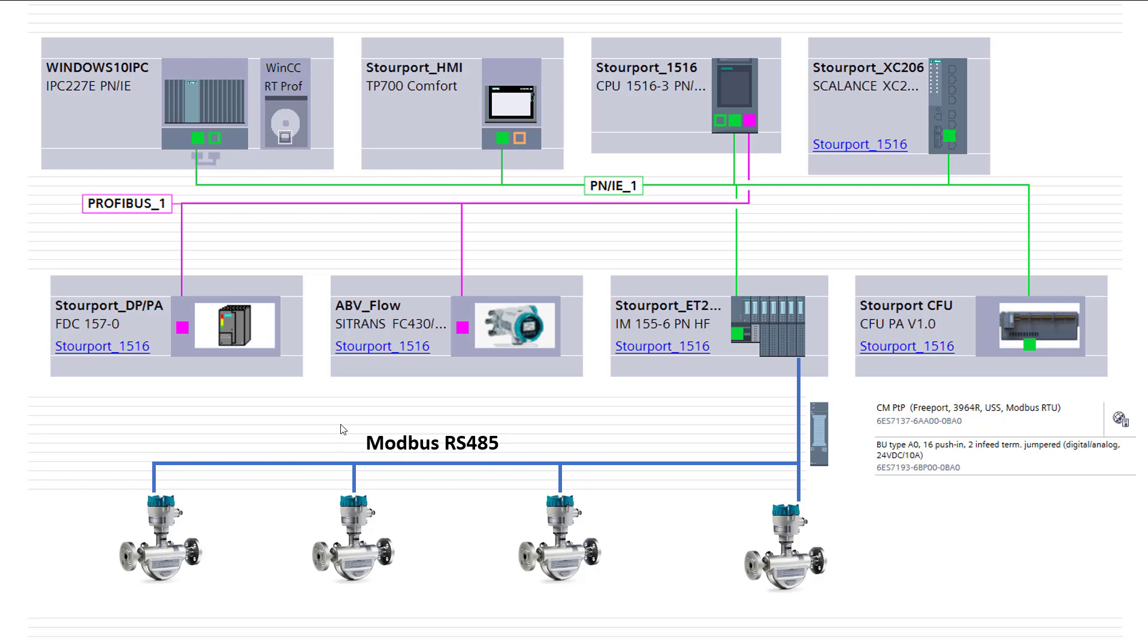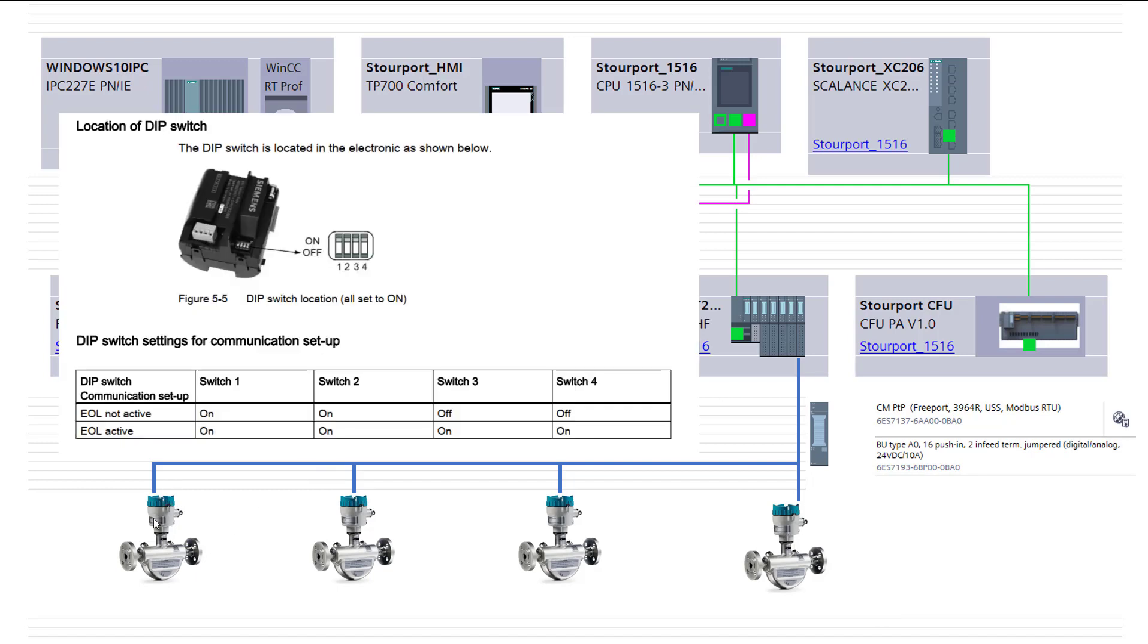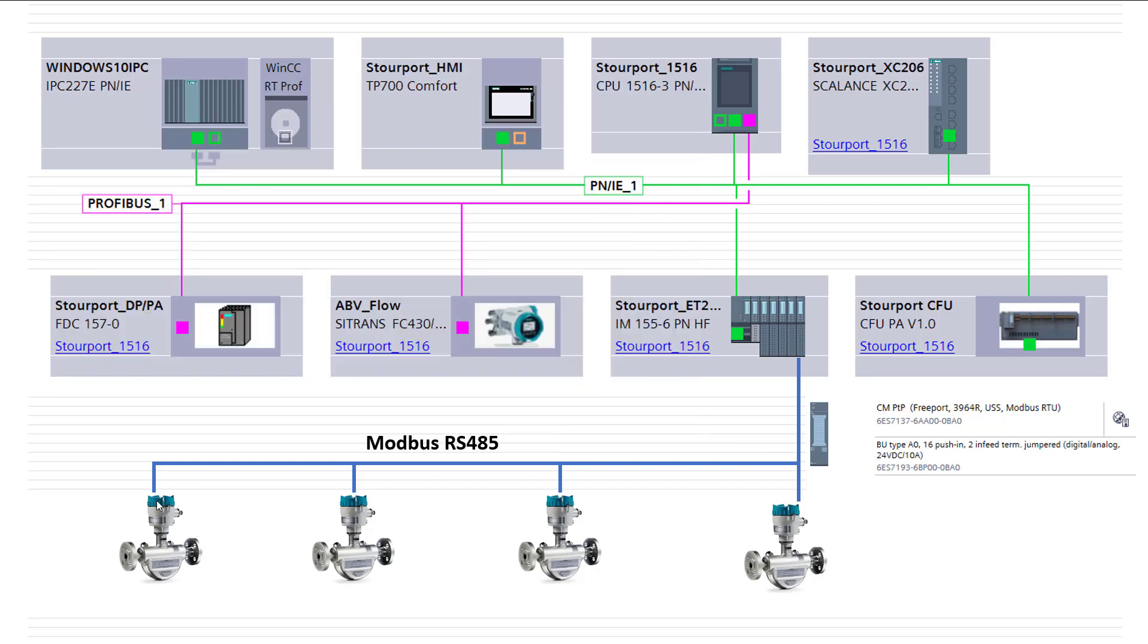While Modbus is a flexible network, it does have some limitations. It gives us the ability to spur off to these instruments, but there are relationships between how long your trunk is—this section at the top we call the trunk, and these go into the instruments we call the spur. So you've just got to be careful with your wiring, your screening has got to be good, and also you have to switch on your end-of-line terminator inside the unit furthest away.